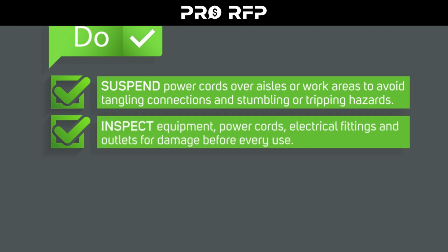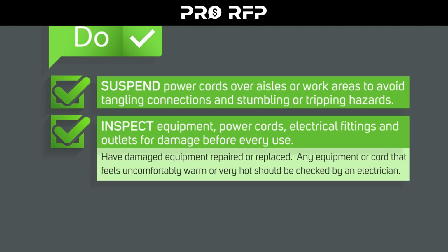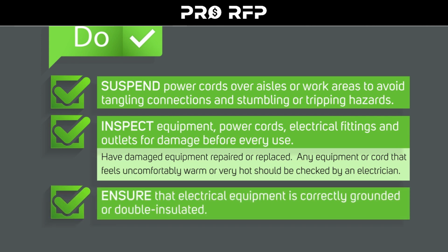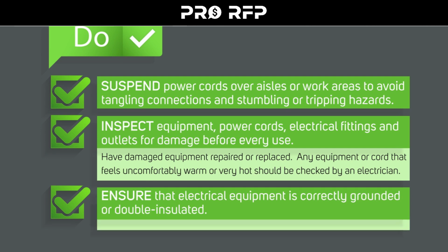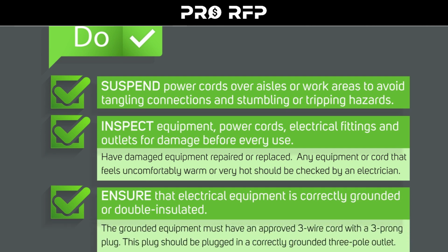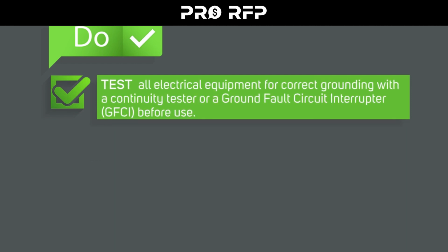Inspect equipment, power cords, electrical fittings, and outlets for damage before every use. Have damaged equipment repaired or replaced. Any equipment or cord that feels uncomfortably warm or very hot should be checked by an electrician. Ensure that electrical equipment is correctly grounded or double insulated. The grounded equipment must have an approved 3-wire cord with a 3-prong plug. This plug should be plugged in a correctly grounded 3-pole outlet. Test all electrical equipment for correct grounding with a continuity tester or a ground fault circuit interrupter, GFCI, before use.